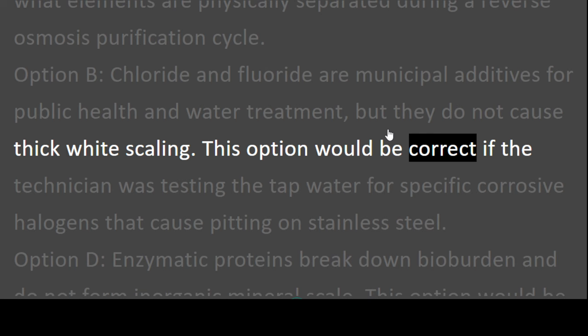This option would be correct if the technician was explaining the active cleaning agent utilized in the first compartment of the manual sink. Concept extension. To physically combat this scaling, the sterile processing department must install mechanical water softening systems to actively exchange these hard calcium and magnesium ions for softer sodium ions before the water ever enters the washroom plumbing.